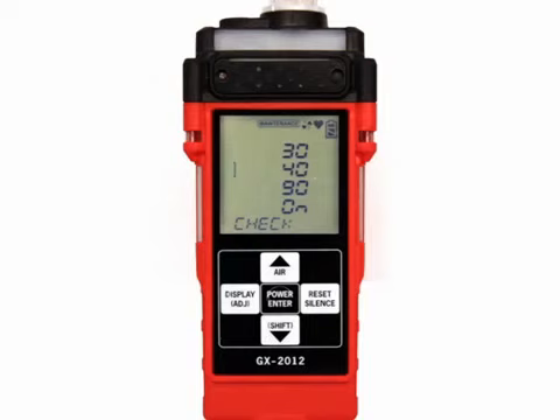To update the cal time setting, use the Shift button to scroll to the cal time value. The factory setting is 90 seconds. This is the length of time the instrument will remain exposed to calibration gas after a failed bump test if AutoCal is set to on. The bump test time is deducted from the calibration time. For example, if the cal time is set to 90 seconds and the gas time is set to 30 seconds, if the bump test fails, the GX2012 will only be exposed to gas for an additional 60 seconds.